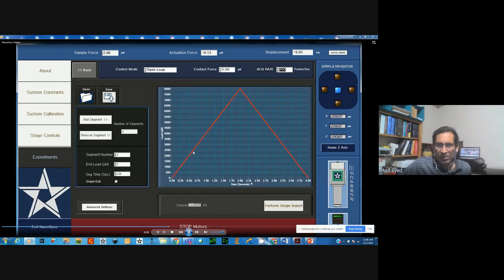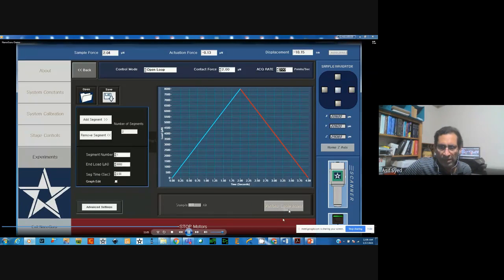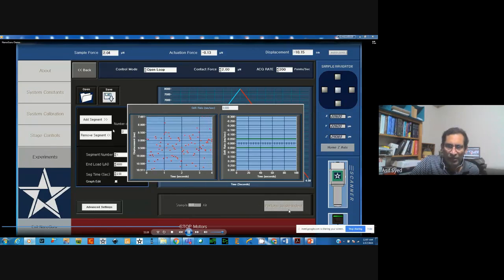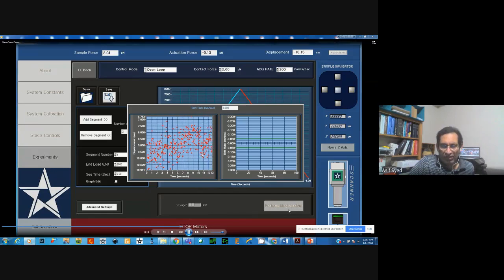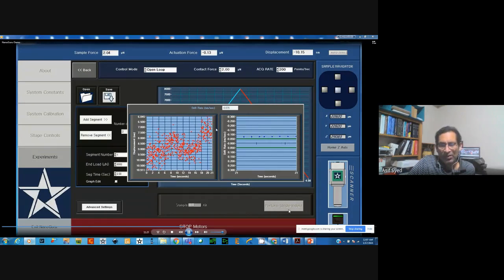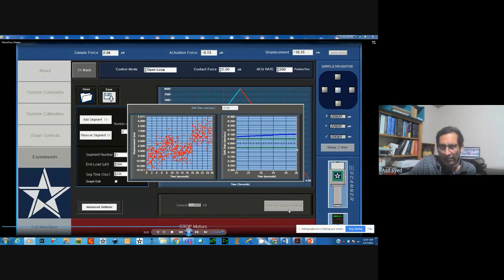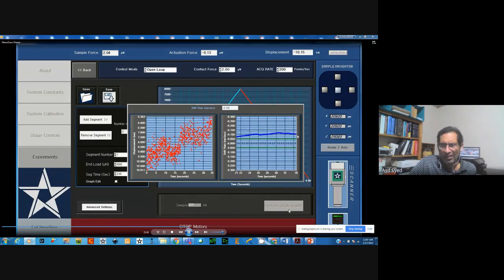Okay, now this is 8000 micronewton load. I'm going to select that as the load that I want to do. It's the first segment, and now let's do a single indent. By performing single indent, you can see this. What you see is basically a window where it is measuring the displacement as a function of time. From the displacement as a function of time reading, it measures the drift. So when the drift reaches a certain number, for example 0.05 in our case, sometimes maybe higher depending upon the room condition, it will immediately start doing the experiment. Here at least now it is about 0.075 or about 0.1 nanometers per second. So when it reaches the parameter that we set as the drift, it will start automatically doing the indent.